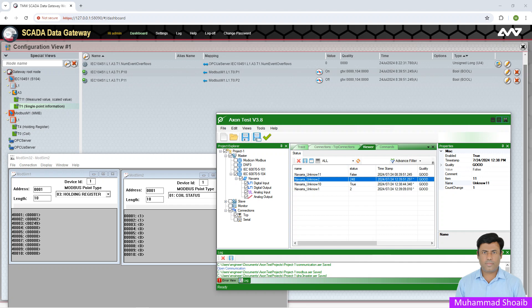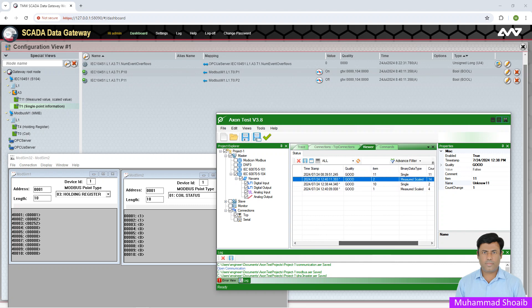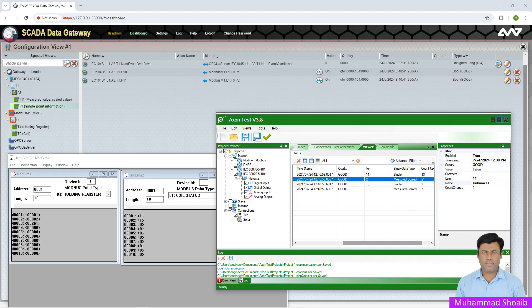That's it for today. To summarize: our purpose was to convert Modbus TCP protocol into IEC 104 protocol. We configured the SCADA gateway as a Modbus master to fetch data from the controller, and at the same time configured the SCADA Data Gateway as an IEC 104 server. The IEC 104 client application then fetches data from the SCADA Data Gateway. That's how we can convert Modbus TCP protocol into IEC 104 protocol. Thanks for watching — please subscribe and like this video.